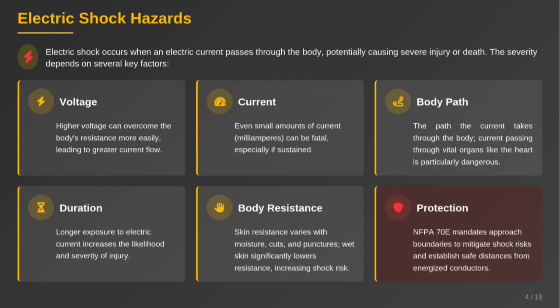Electric shock occurs when the body becomes part of an electrical circuit. The severity depends on 6 factors: voltage, current, exposure time, body resistance, the current's path, and the level of protection used. Even a small current, just a few milliamps, can be fatal if it travels through the heart. That's why NFPA 70E defines approach boundaries, specific safe distances workers must maintain from energized parts to avoid shock.